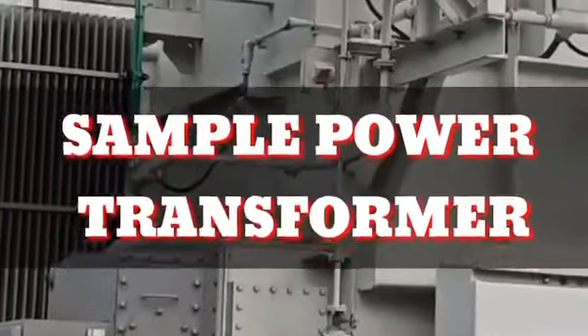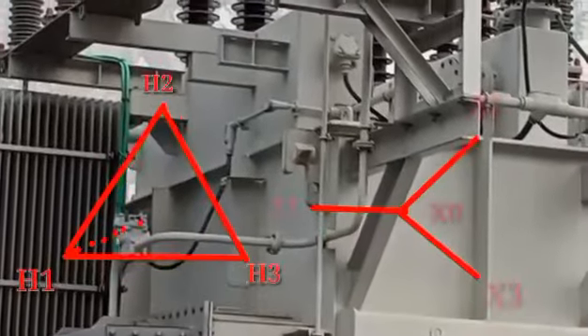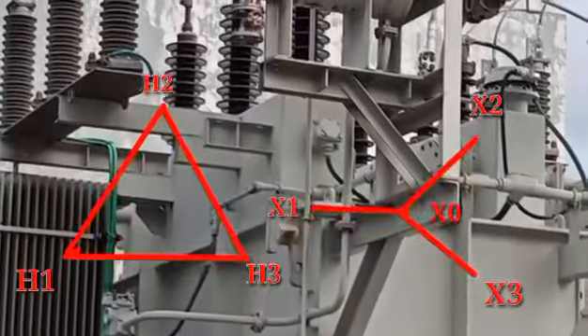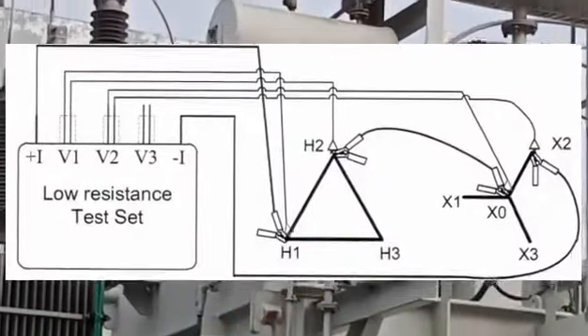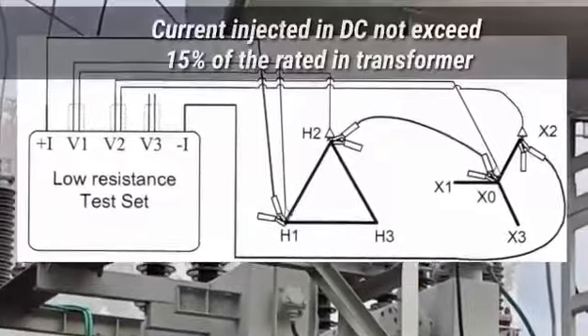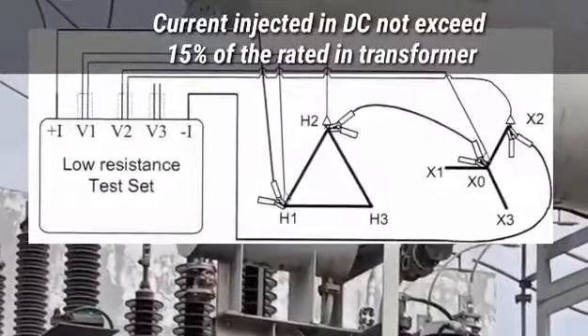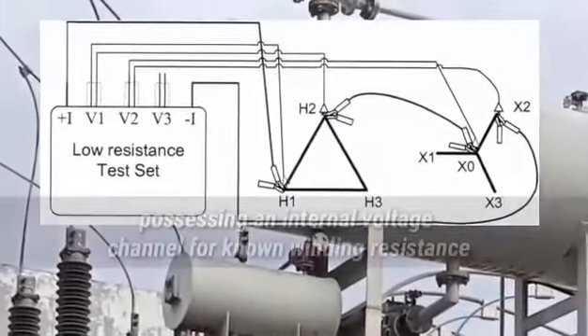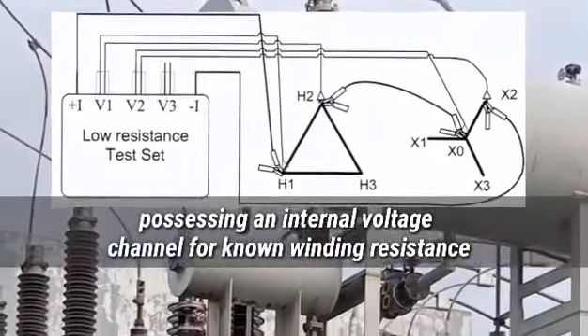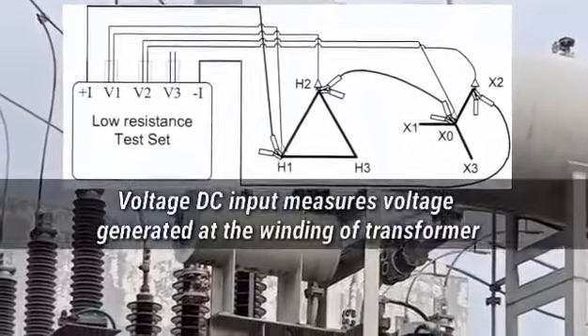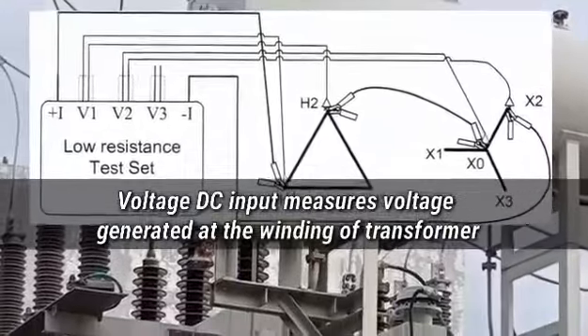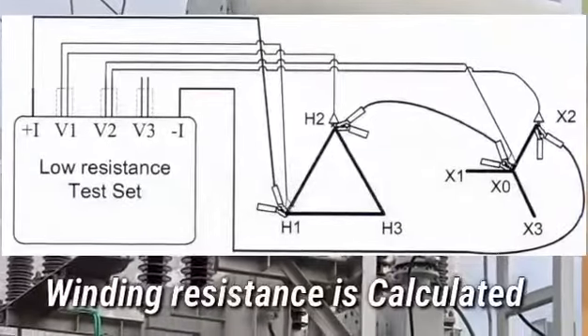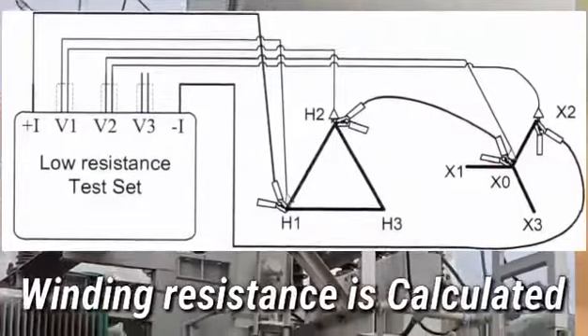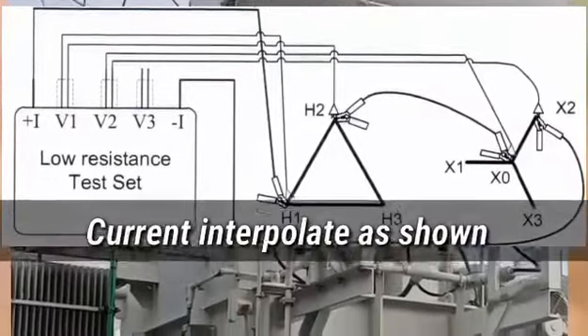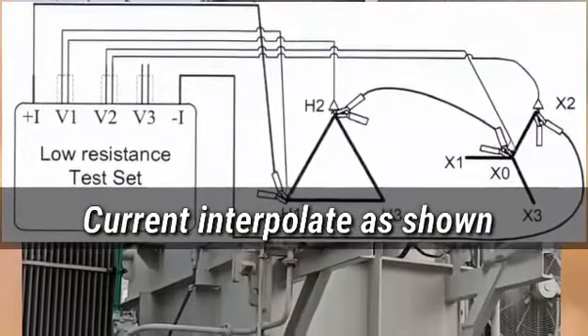Just like in this example of the power transformer having a delta-connected primary winding and a Y-connected secondary, a low resistance test set is connected accordingly. The current to be injected is DC, not exceeding 15% of the rated current of the transformer, and the set possesses an internal voltage channel to determine the winding resistance. The voltage DC input measures the voltage generated at the transformer winding. From that value, the winding resistance is calculated. As a basic test exhibited in this video, the current is injected to H1-H2 and X0-X2.